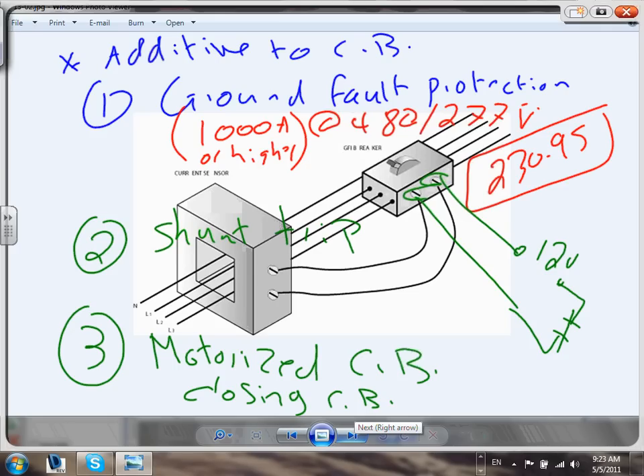You can also add auxiliary contacts to a circuit breaker. Every time the breaker opens or closes, it sends a signal — for example, to a monitoring system. At Commons Field, when a circuit breaker tripped, the display turned from green to red. That came from auxiliary contacts: when the breaker closes, a contact closes and energizes a green indicator light; a normally-closed contact provides a red light when the breaker is open. These control features for power circuit breakers are essentially unlimited.